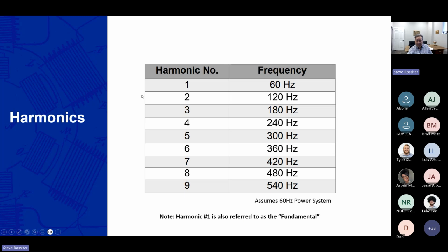When you think about our 60 hertz grid here in the US, 50 hertz in Europe, the fundamental frequency is 60 hertz. If you now have 180 hertz on that waveform, which would be a single phase third harmonic, or a fifth harmonic, which would be at 300 hertz, now you're starting to add other waveforms that are riding on top of that 60 hertz. And that's exactly what's starting to happen when you start putting electricity through silicon.